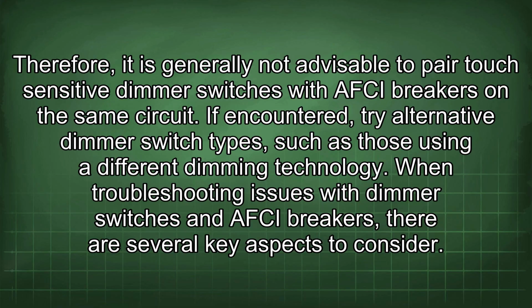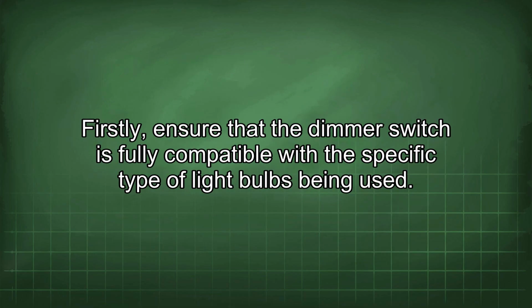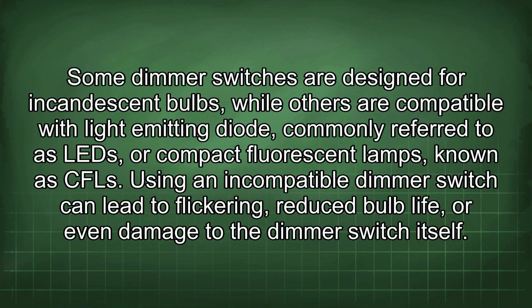When troubleshooting issues with dimmer switches and AFCI breakers, there are several key aspects to consider. Firstly, ensure that the dimmer switch is fully compatible with the specific type of light bulbs being used. Some dimmer switches are designed for incandescent bulbs, while others are compatible with light-emitting diode, commonly referred to as LED, or compact fluorescent lamps, known as CFL. Using an incompatible dimmer switch can lead to flickering, reduced bulb life, or even damage to the dimmer switch itself.